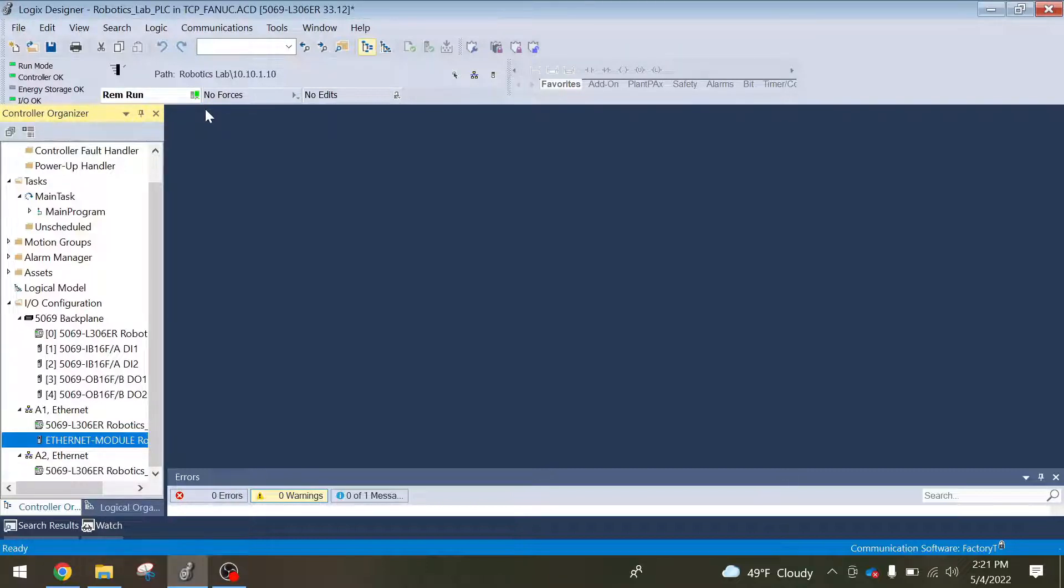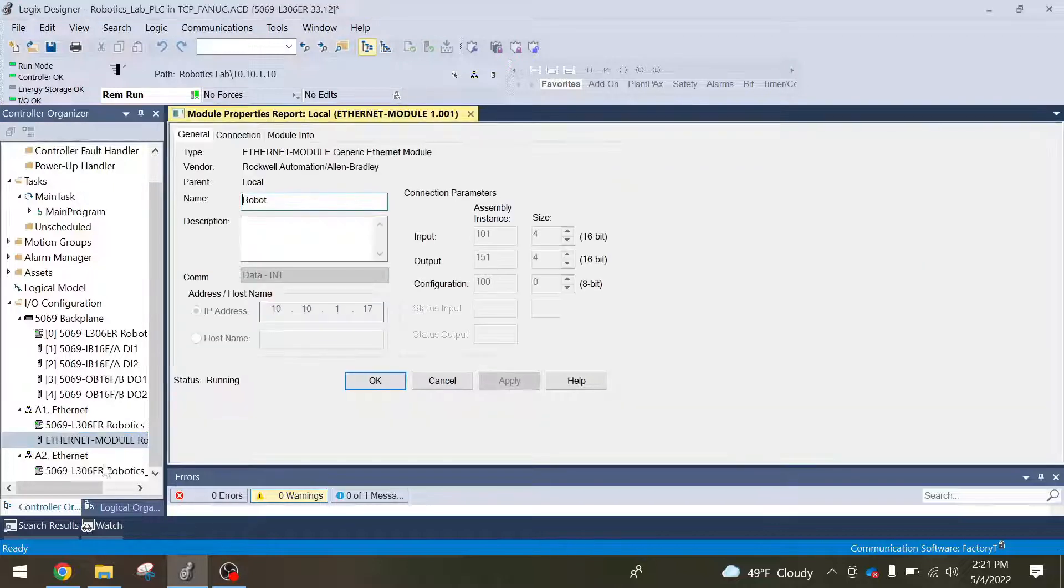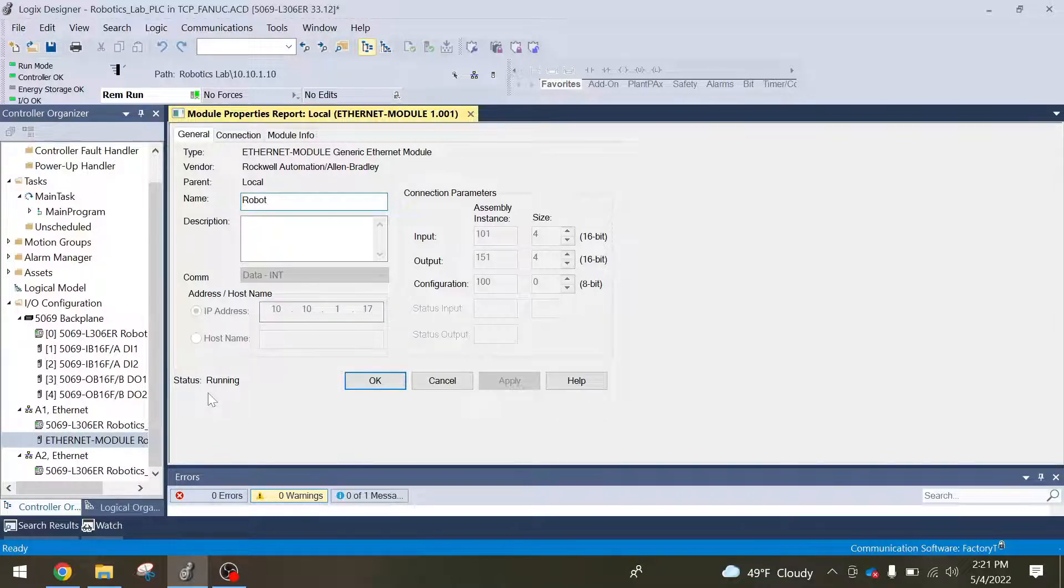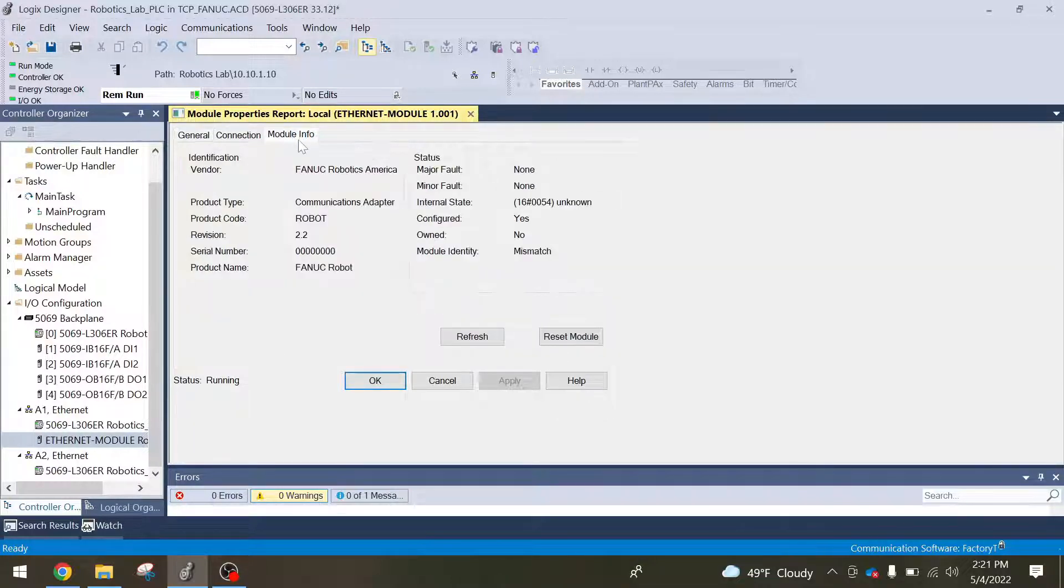Now I'm in run mode on the PLC and you see I don't have any errors here. I double click the module and you can see right here status is running. That means everything connected is fine. If I go to module info, you can see everything auto-populated there as well.